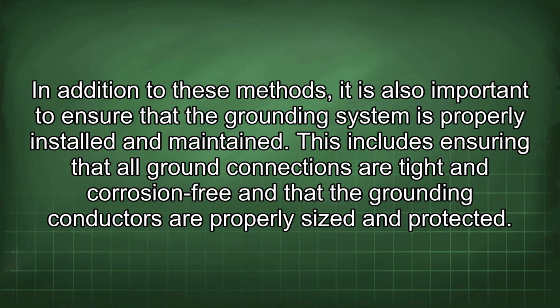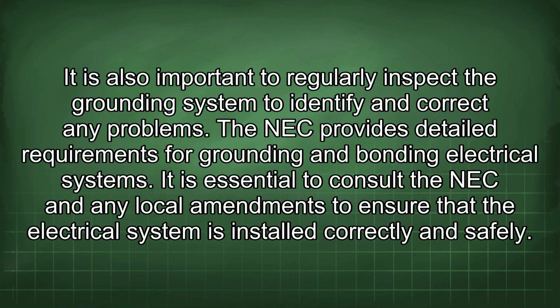maintained. This includes ensuring that all ground connections are tight and corrosion-free and that the grounding conductors are properly sized and protected. It is also important to regularly inspect the grounding system to identify and correct any problems. The NEC provides detailed requirements for grounding and bonding electrical systems.